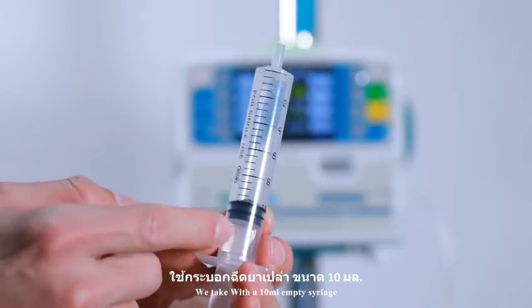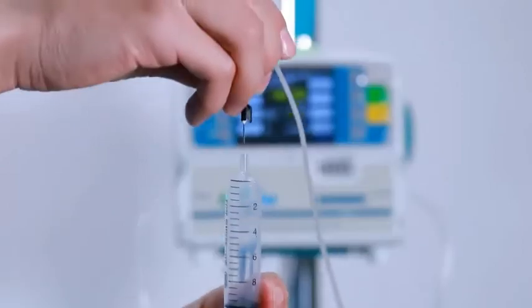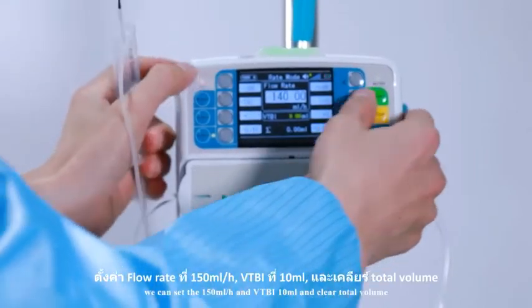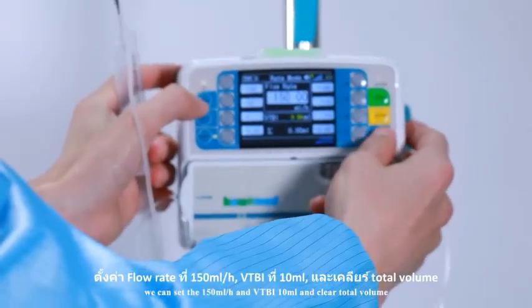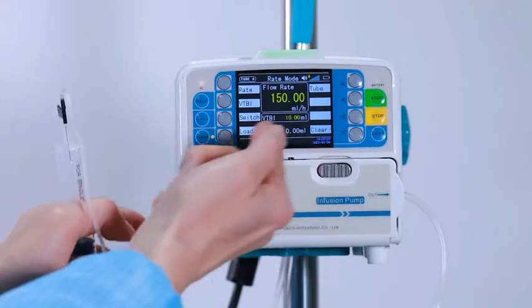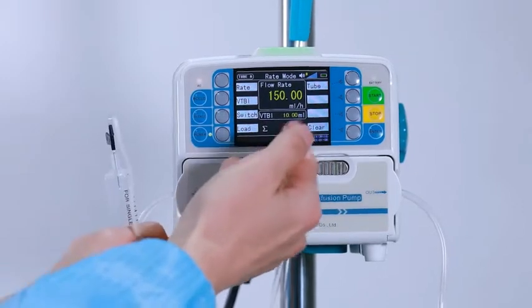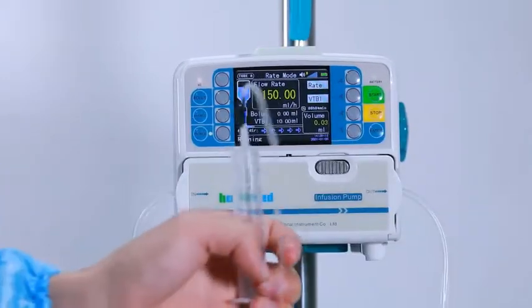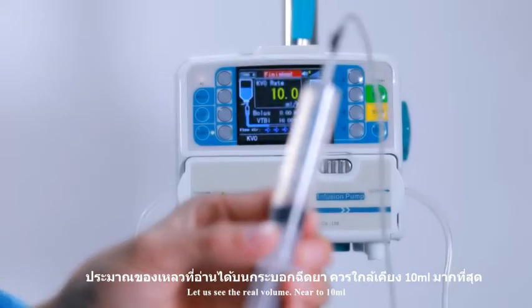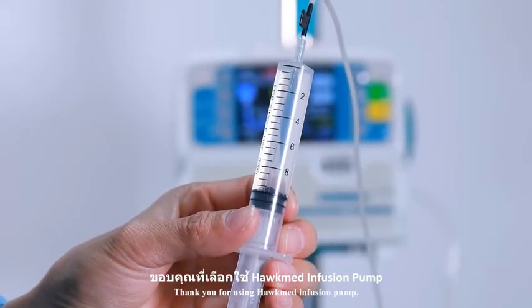We take a 10ml empty syringe and insert the needle. We can set 150ml per hour, VTBI 10ml, and clear the total volume. Then press start. Let us wait for 4 minutes and see the real volume — near to 10ml, 100% accuracy. Thank you for using Hawkmed infusion pump.